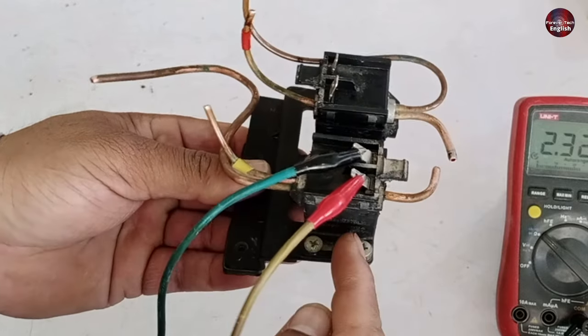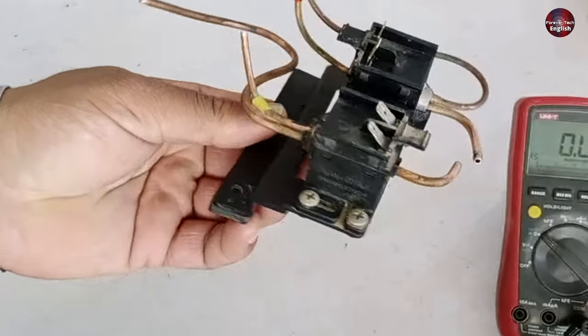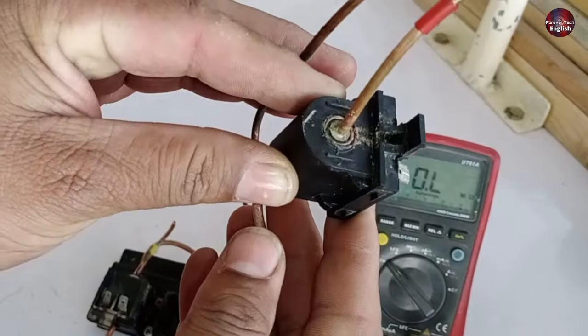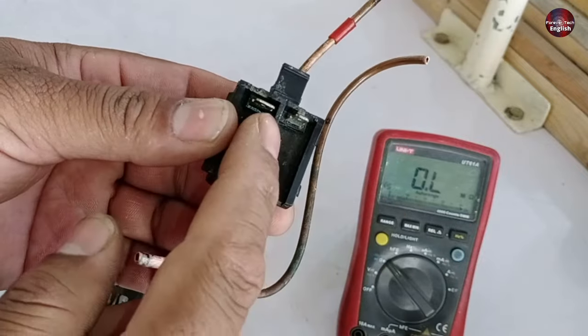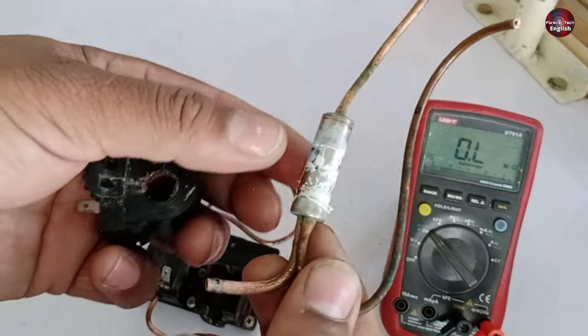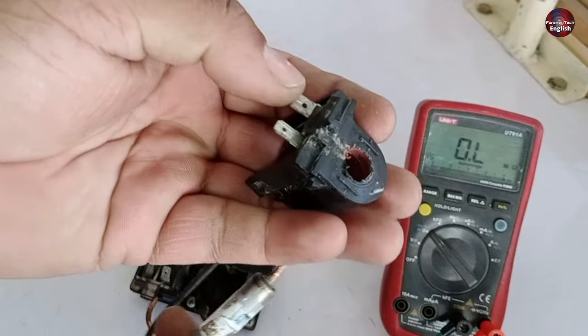I will replace these valves with new ones. The question is whether these electromagnetic valves are repairable or not. I have opened them from the top — it is a solid piece made of plastic with a coil inside. If the coil burns out, you can replace the coil if you have the same coil available. Take the coil out and replace it with another. If the plunger goes bad, it can also be replaced. However, repairing the plunger from the inside is not possible, nor can the coil itself be repaired.